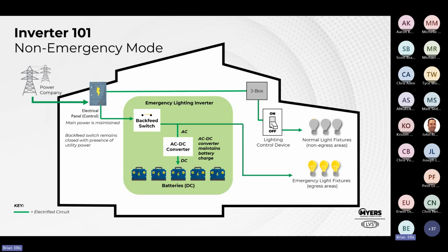Now this lighting control device can control my normal lights, right? So I meet ASHRAE IECC Title 24. The problem is we want to switch the emergency as well. How do you do that? How do you take a switch on utility and everything downstream from this inverter now is emergency, right? So this is utility, this is emergency. So this switch can't actually control both. So we have to add in a new device.